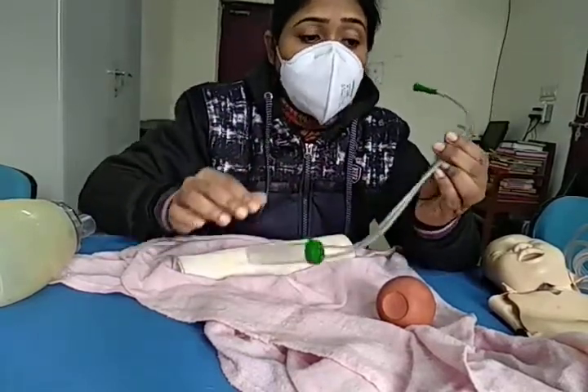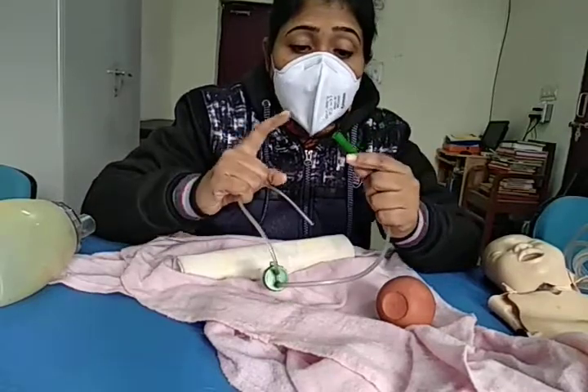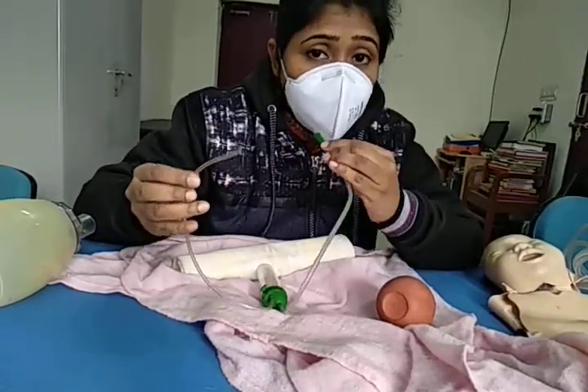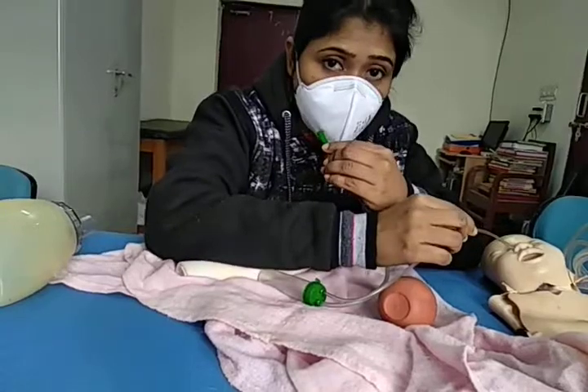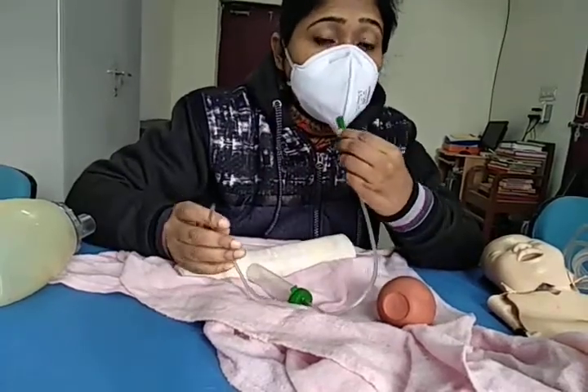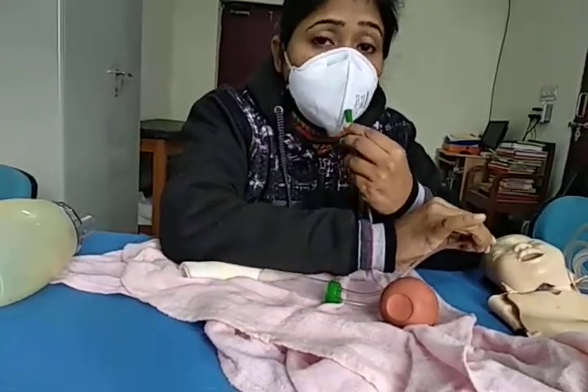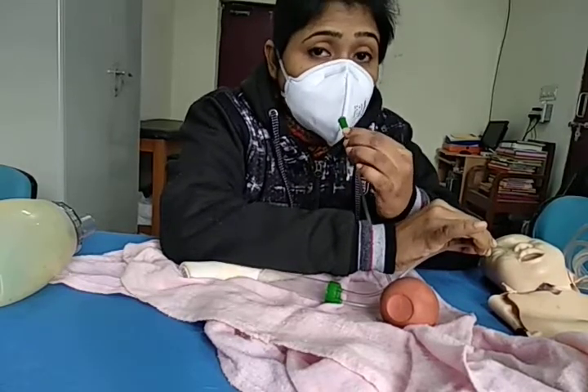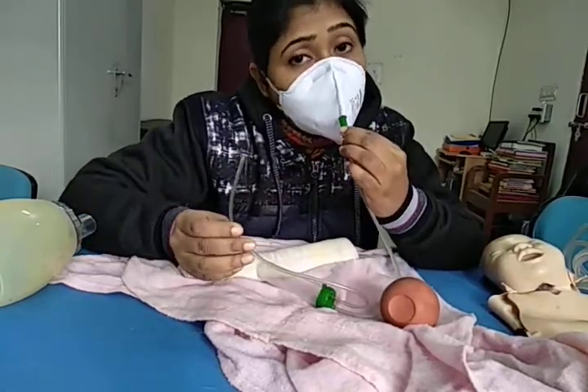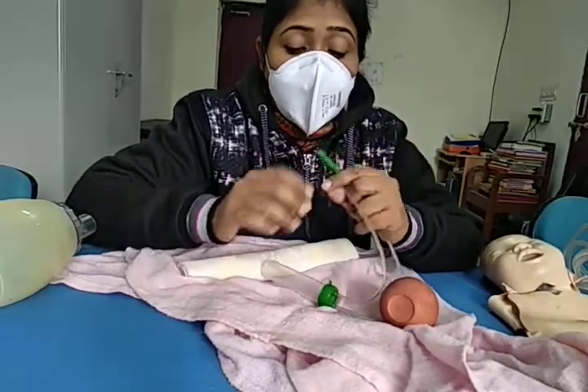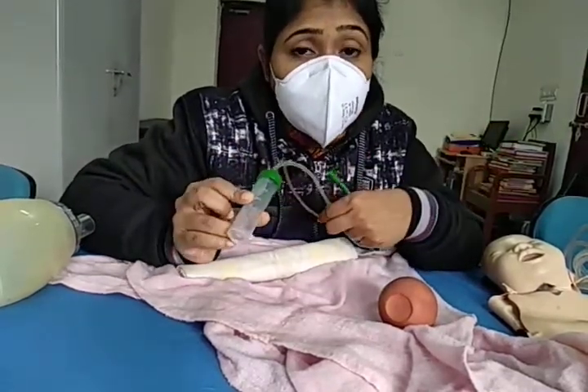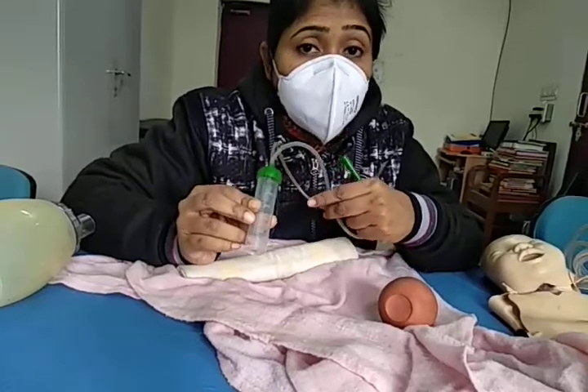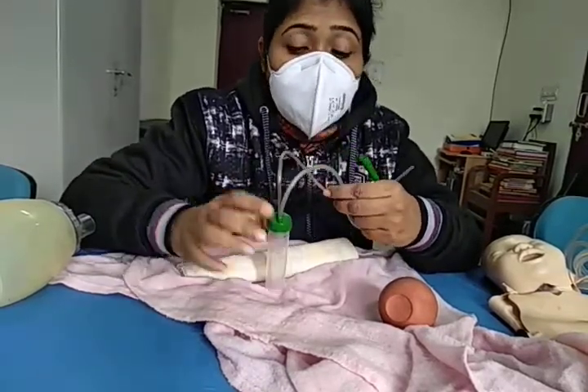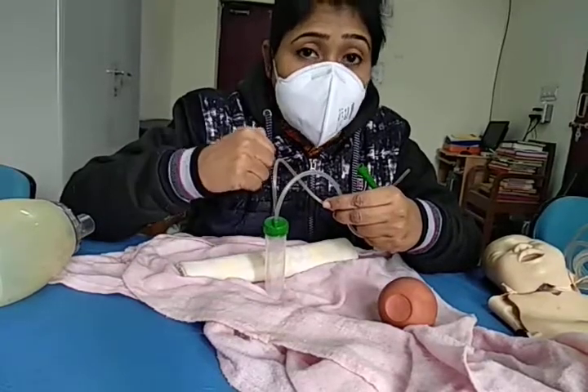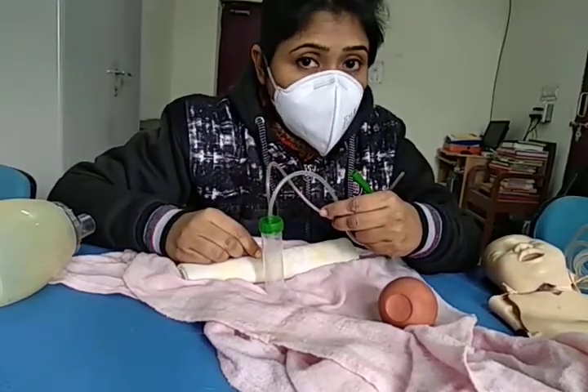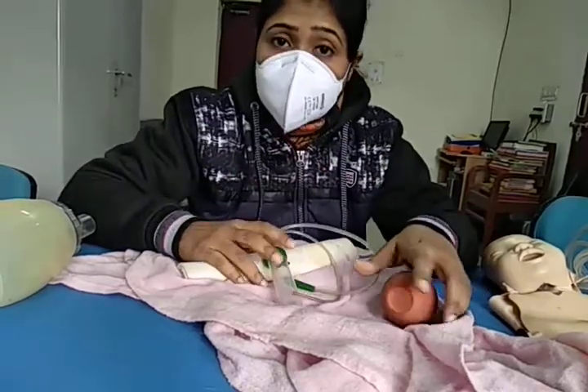It has a chamber and 2 tubes. The green end goes to the resuscitator's mouth and the other end in the baby's mouth. So first we put the baby's end in the baby's mouth. Then we create a negative pressure and take out the tube in negative pressure. And the minimum volume of this chamber should be 20 ml, because if it is less than that, then the fluid can be regurgitated in the resuscitator's mouth. So this is the sucker.